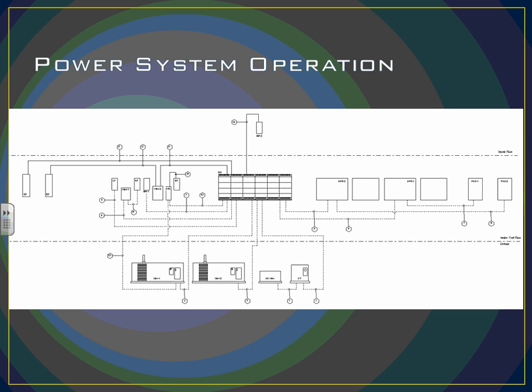Okay, so upon emergency power, as soon as we're sensing that power is lost from the utility side, our ATS is going to transfer power from the utility side over to the generator side. Included with that, for the UPS and the PDUs, we have our battery banks. So we're going to be able to hold power for the 15 minutes or whatever it takes for the generators to hold in line and take over power for our data center backup power. In the meantime, our generators are going to start flowing power into emergency panels so that we have lighting and everything for that. And then these will cycle up and take over the power for the entire system at that point, with 100% of the power transfer. So the ATS, obviously, is the most important thing in there for the direct connection for switching from emergency power to the generator power. And at that point, you're going to strip it off of emergency power.